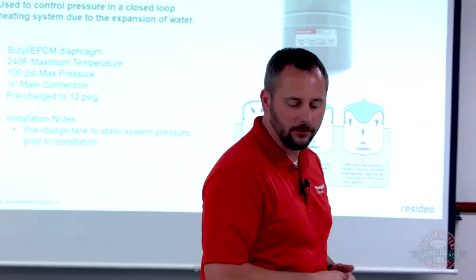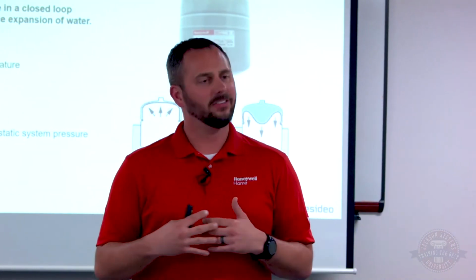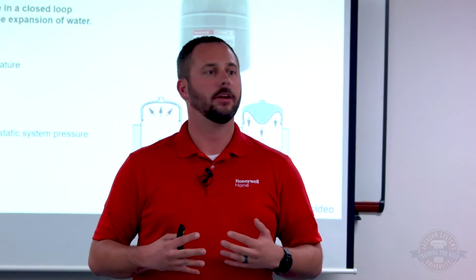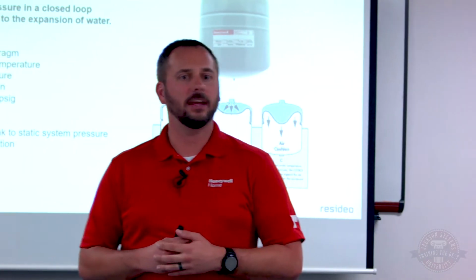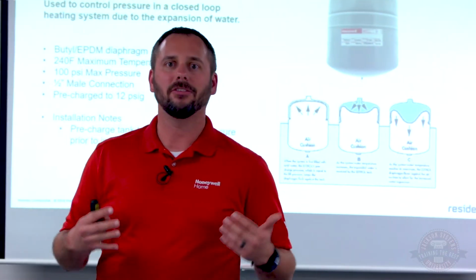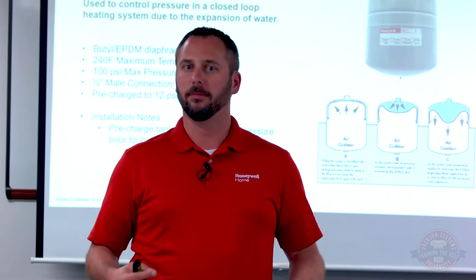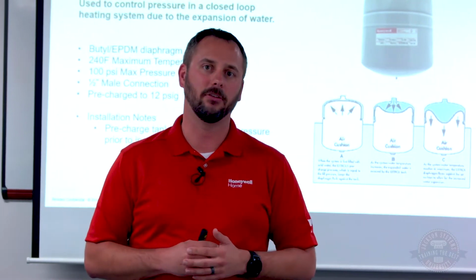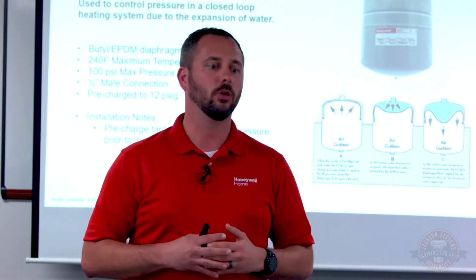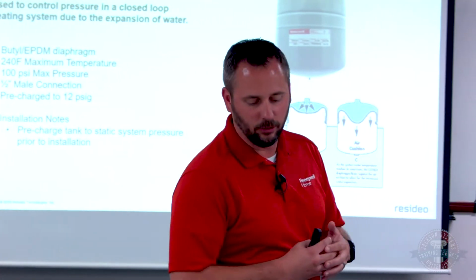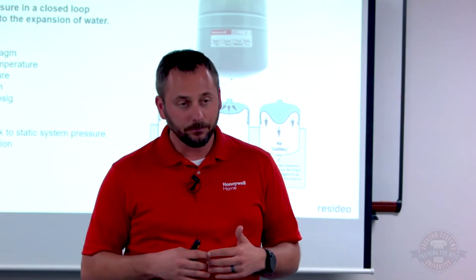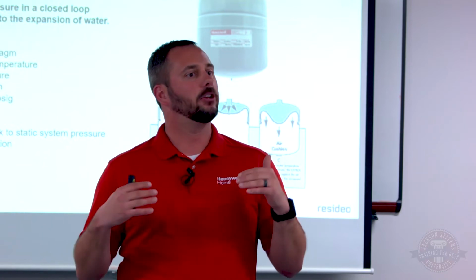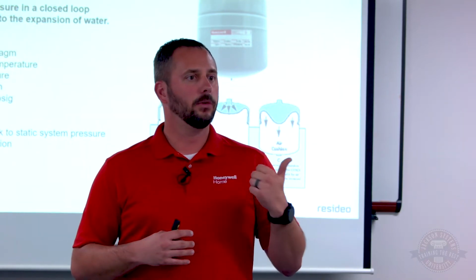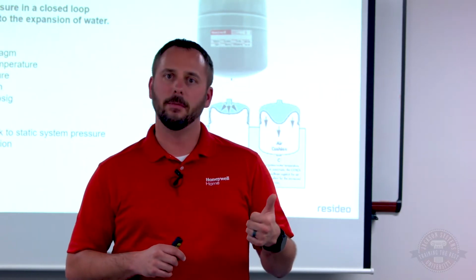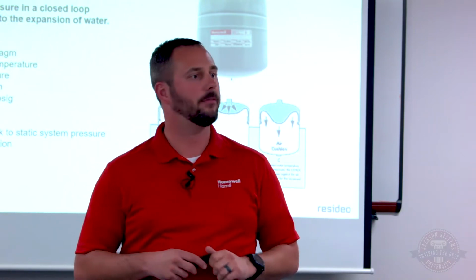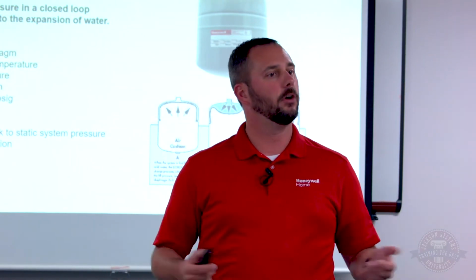And then on the expansion tanks, everything's kind of sized for 1/2 inch on your water makeup in a hydronic heating system. If you get an expansion tank that's 3/4 inch, more than likely that's a domestic potable water expansion tank and not a hydronic heating expansion tank. The diaphragms are different between the two. In a hydronic expansion tank, we use butyl and EPDM diaphragms that have 1/2 inch male connections on the top. If you look at our air eliminators, you're going to see 1/2 inch female connections on the bottom. Expansion tanks are 1/2 inch male connections on the top. And all of our fill valves are going to be 1/2 inch.